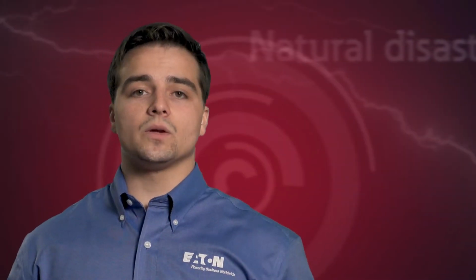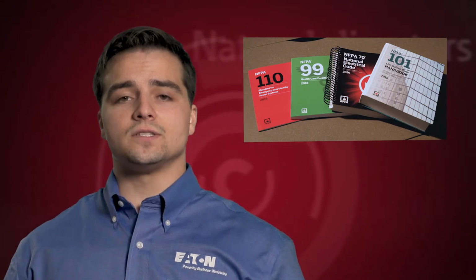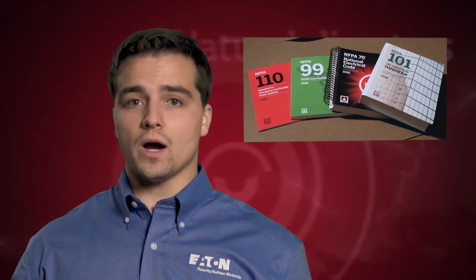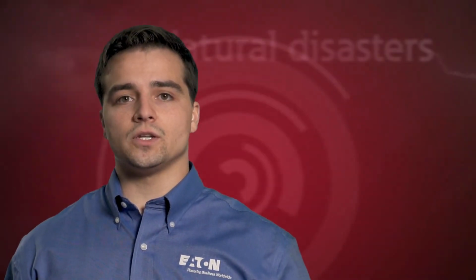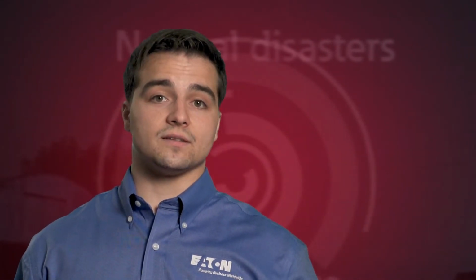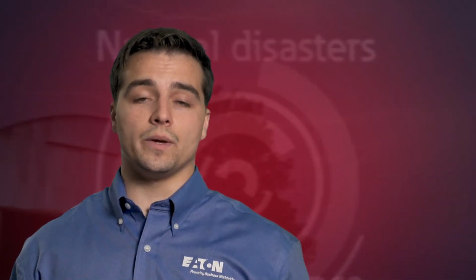At Eaton, we typically work with our customers to go beyond minimum requirements for such systems to help account for unexpected events. While safety codes typically address minimum emergency power requirements, other factors we've mentioned may not be accounted for, and additional power system backup may be required for systems such as imaging and diagnostic equipment within a hospital.